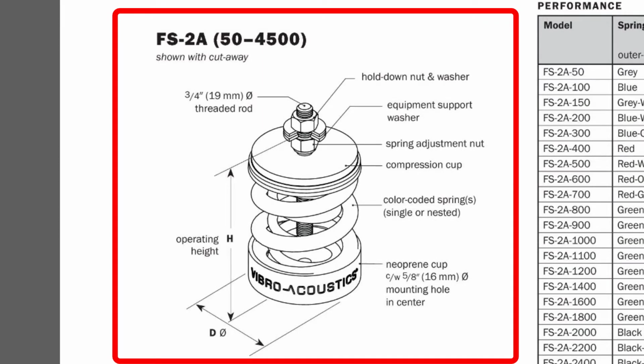A couple of important dimensions are labeled here: the diameter of the support rod that attaches to the equipment, or inertia-based support bracket in this case, and the hole diameter in the bottom cup for attaching to the floor should they choose to do so. The diameter of the rod is important to know since the hole at the support point must be large enough to allow the rod to pass through.